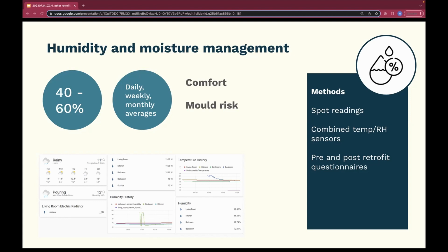You could also take on-the-spot readings, if you were doing an assessment, for example, or you could do data loggers or longer term monitoring for this kind of thing. That's useful as well if you want to check how your ventilation improvements are doing. Obviously, if you've got prolonged periods of higher humidity, or the peaks are not dropping that quickly, then it might indicate an issue that warrants some investigation.